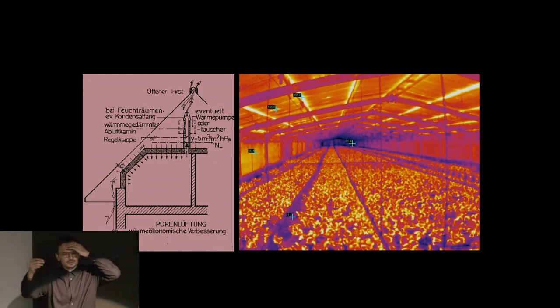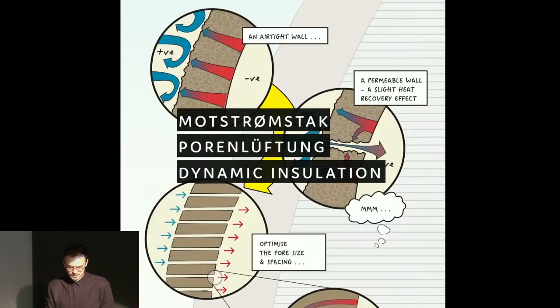So the idea is that you need to suck air in, and you can do that using a fan or natural suction from a chimney. As you increase the airflow, the conduction losses to the environment reduce - a kind of dynamic U value, if you would. The essence of this idea goes back to the 1960s, when engineers in Northern Europe first experimented in livestock buildings by sucking fresh air through insulation materials in walls and ceilings. The Norwegian phrase highlighted the novelty of countercurrent heat exchange, while in German, a term alluded to the idea of breathing with ventilation through pores.